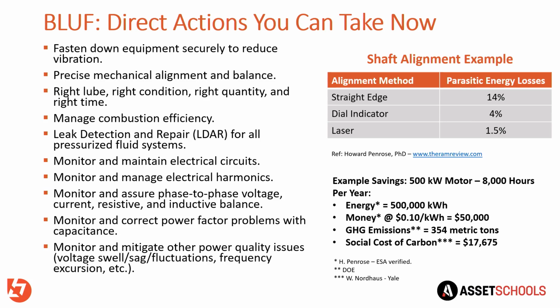After 2 days, we were able to shut off 2 compressors. So we had 10 run at full tilt. After 2 days, we were able to shut down 2. And once we got back to some of the couldn't fix as found leaks, they shut down a 3rd compressor. So they were running 10 compressors when they only needed 7. That's a tremendous amount of energy. Plus they were able to cancel that order for 2 more compressors. So they were about to add 2 more compressors.